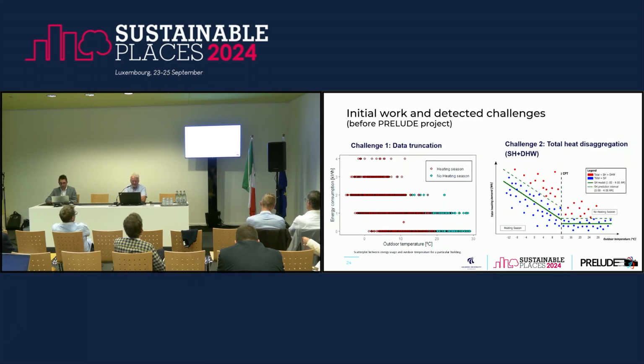This illustrates the two challenges I mentioned. The challenge of truncation errors in the data is quite important in buildings where energy use is low, such as highly efficient buildings. If you only have an energy use of 1 or 2 kilowatt hours per hour, truncation can have a big influence on accuracy, while if it was 10 kilowatt hours per hour, the difference would be smaller.